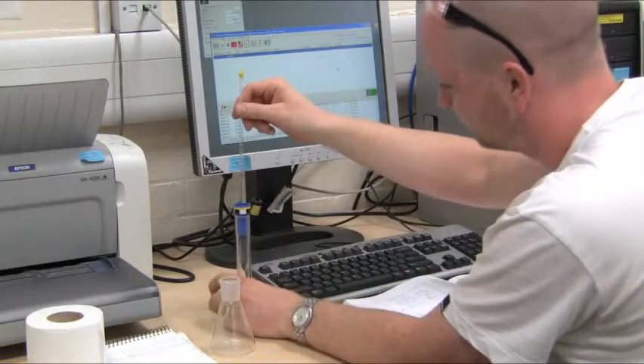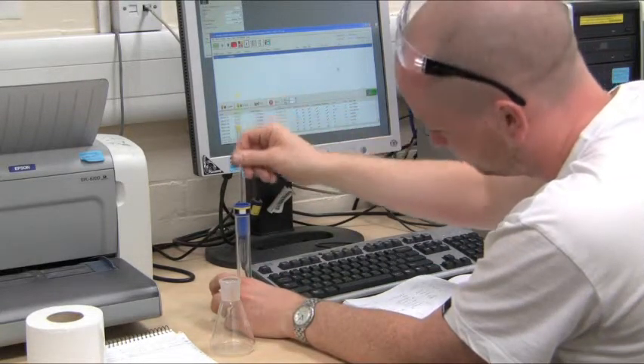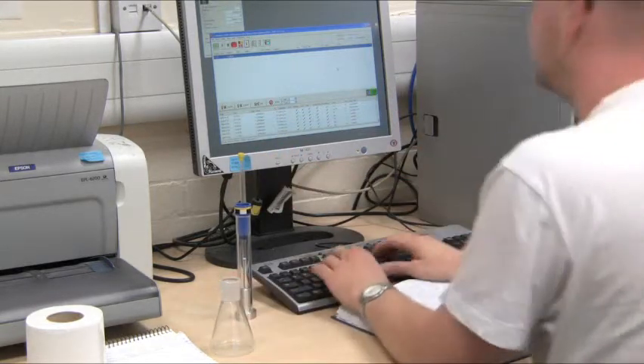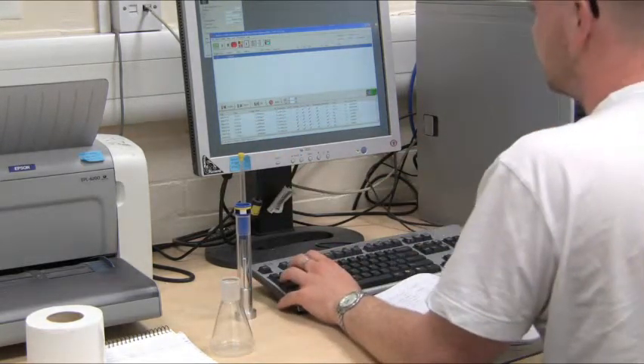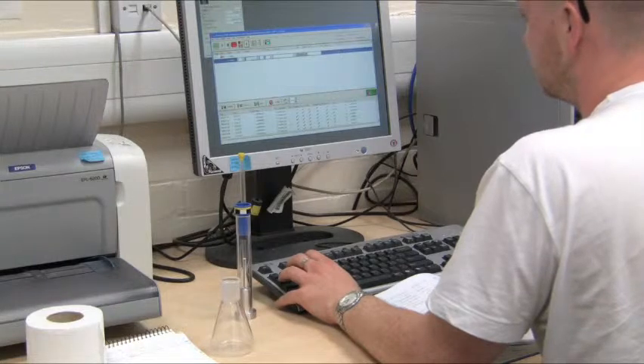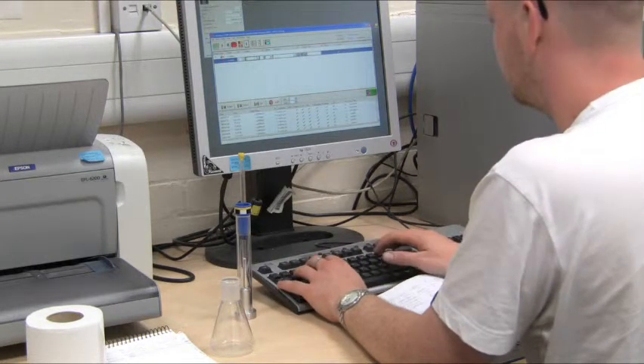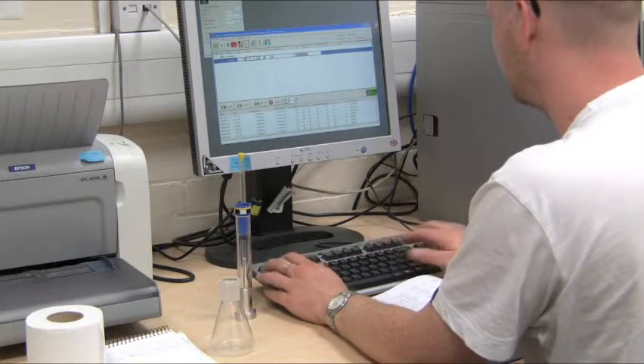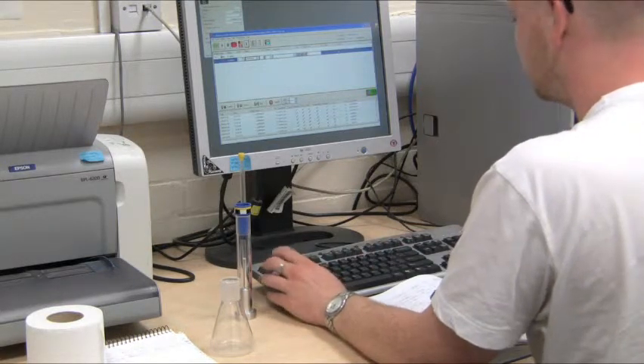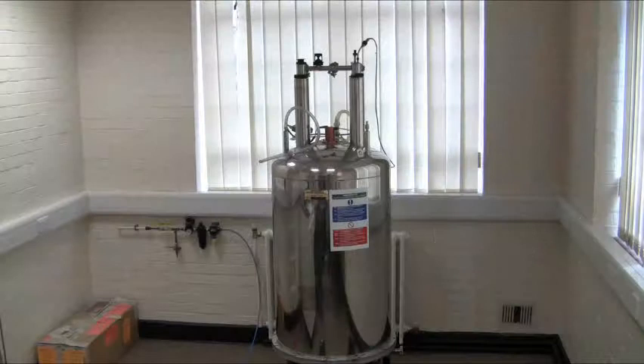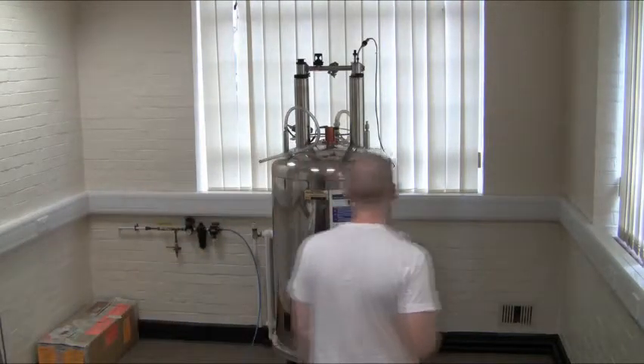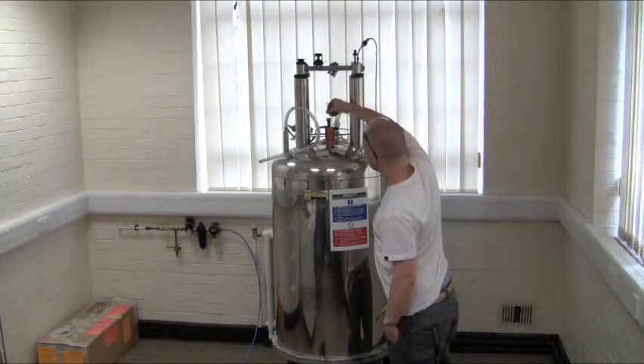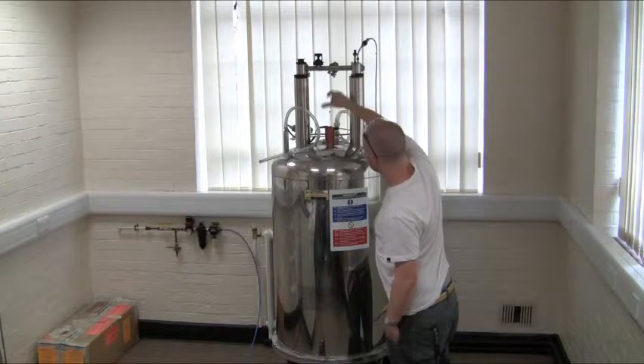After cleaning, the sample tube containing the sample is loaded into a spinner. A spinner houses the sample tube during spectrum acquisition and protects it, allowing it to be rotated within the coil. The details of the sample to be run are entered onto the operating computer. The sample in the spinner is then placed above the magnet and lowered into the magnetic field on a cushion of compressed air.